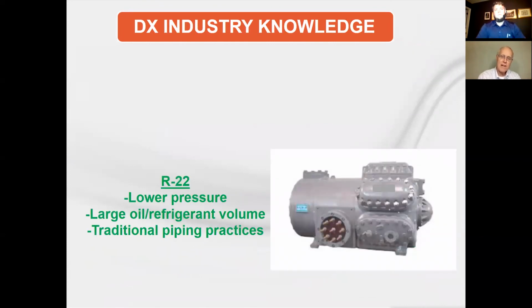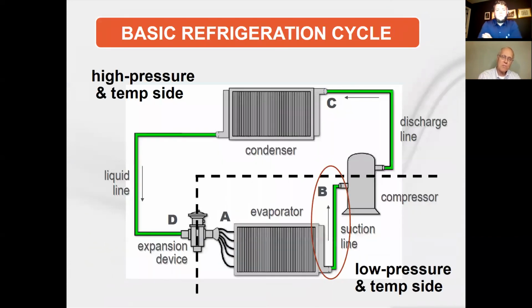What's involved, a lot of data centers use this on computer room units where you'd have another device right where it says liquid line. You'd have a tank of refrigerant there, a receiver full of liquid. And there'd be another valve that would go from where the discharge line is, that would send hot gas from the compressor discharge over to that receiver, and it would pressurize that receiver with hot gas to force liquid down to the expansion device.